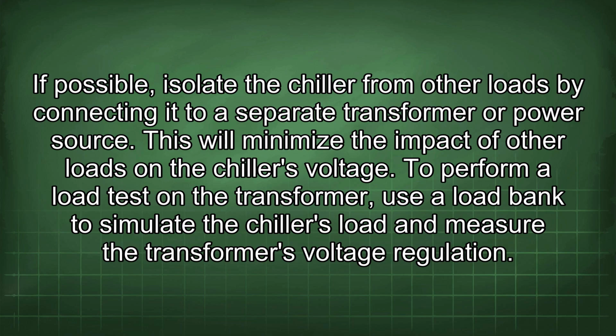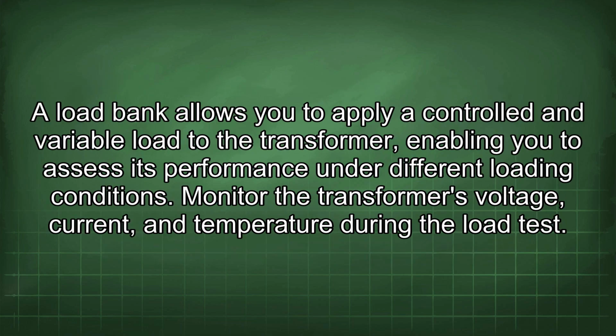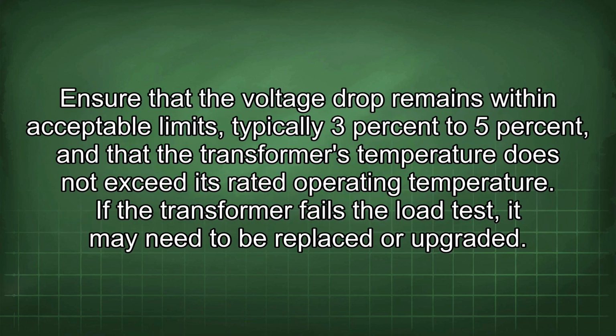To perform a load test on the transformer, use a load bank to simulate the chiller's load and measure the transformer's voltage regulation. A load bank allows you to apply a controlled and variable load to the transformer, enabling you to assess its performance under different loading conditions. Monitor the transformer's voltage, current, and temperature during the load test. Ensure that the voltage drop remains within acceptable limits, typically 3% to 5%, and that the transformer's temperature does not exceed its rated operating temperature. If the transformer fails the load test, it may need to be replaced or upgraded.